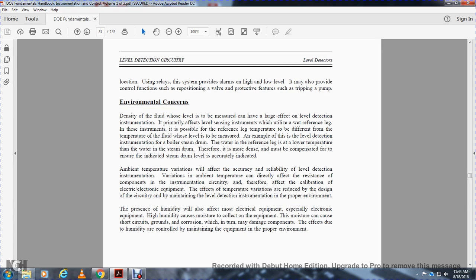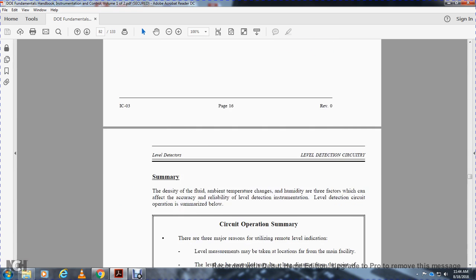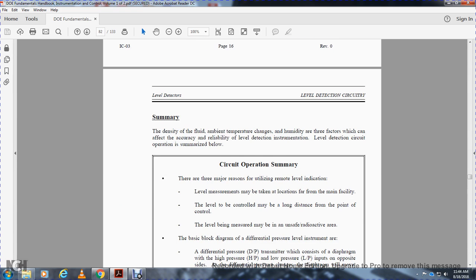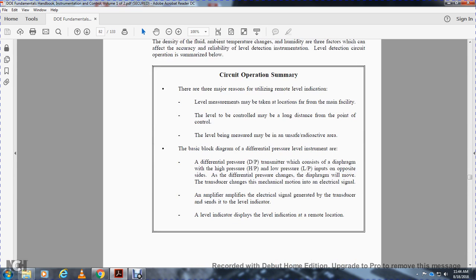High humidity causes moisture to collect on the equipment. The moisture can cause short circuits, grounds, and corrosion, which in turn may damage the components. Humidity control will maintain the equipment in a proper environment. The density of the fluid, ambient temperature change, and humidity are three factors which affect the accuracy and reliability of level detection instrumentation. Level detection circuitry operation is summarized below.